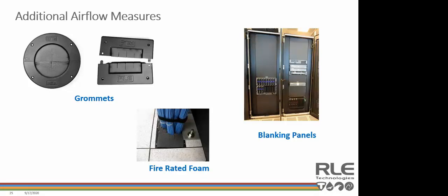Every facility has those small spaces where airflow is an issue, whether it's cabling holes in the flooring from a previous facility configuration or narrow spaces between the flooring and the racks. Use RLE foam to fill these small spaces and gaps, in turn optimizing your facility's airflow. We sell these in 24 by 24 by 2 sheets, which are pre-scored to 1-inch rows, so you can quickly separate out just enough to fill the pesky gaps in your infrastructure.